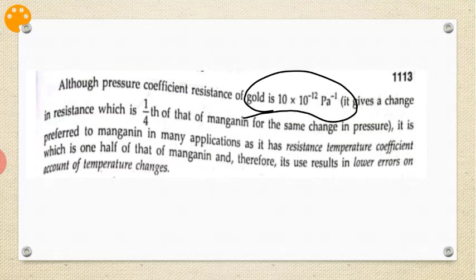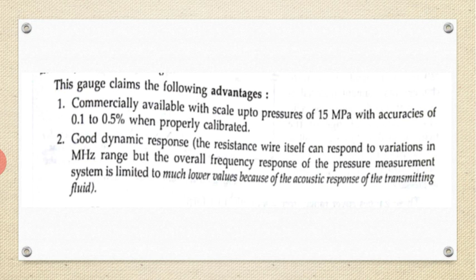The pressure coefficient of resistance of gold is 10 into 10 raised to minus 12 per pascal. It gives a change in resistance which is 1/4 of that of manganin for the same change in pressure. So gold is preferred over manganin. Some of the advantages are a scale up to a pressure of 15 megapascal, accuracy of 0.1 to 0.5% when properly calibrated, and good dynamic response.